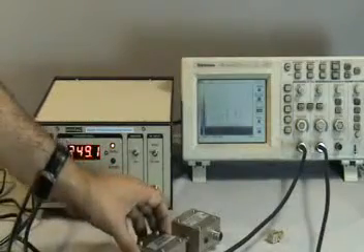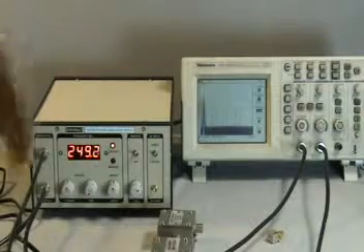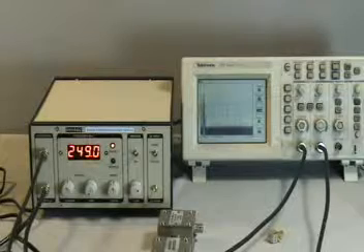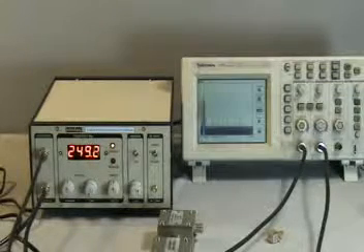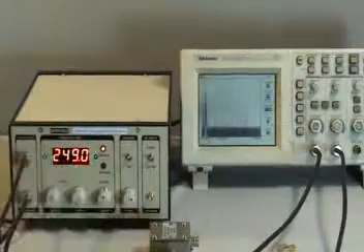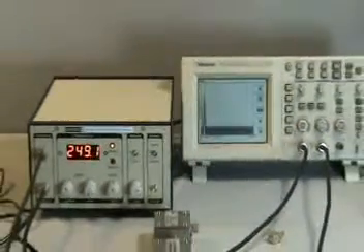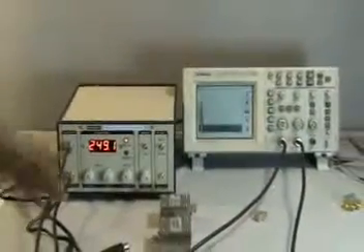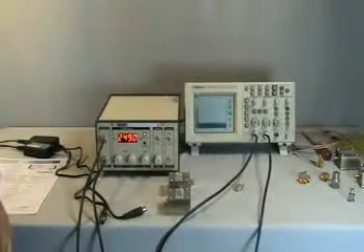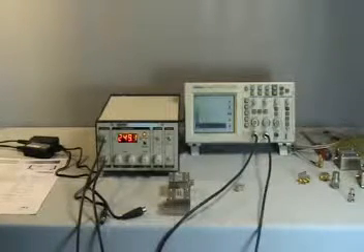We have also provided an excess noise generator with a calibrated excess noise above the 25 degrees thermal noise level of 12 dB. Hence its level is 12 dB above the thermal noise floor at 25 degrees Celsius. We've also provided some antennas, some low pass and high pass filters, and some terminations for you to experiment with. Now we start off with the working of the instrument.